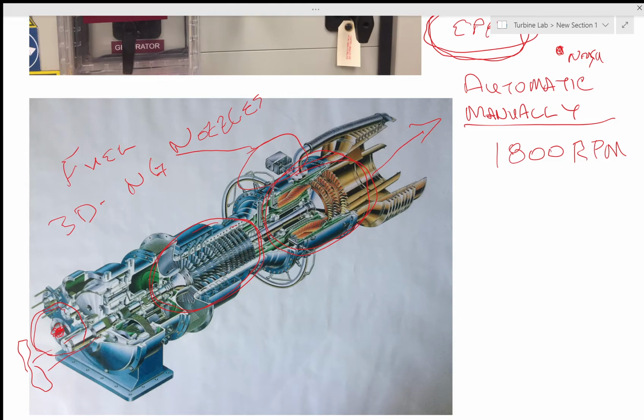That's a cutaway picture of our turbine. It has a transmission. Basically, this motor fits in there, turns those gears, and cranks up the motor. The turbine starts spinning at just under about 1725 RPM, non-synchronous speed. Then they start upping the field current, and once they get field current on there, it comes up the remaining 75 RPM and picks up to synchronous speed.